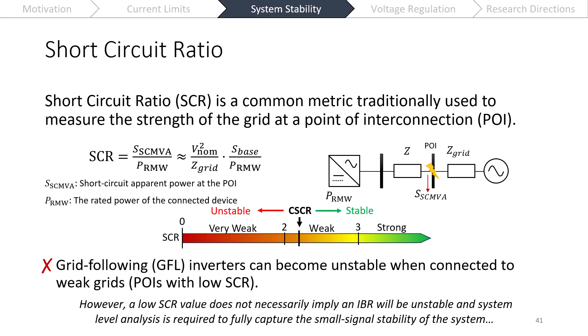And to actually be able to understand stability, we have to do more of a system-level analysis, considering how devices might interact, and then also derive something called the critical short circuit ratio, which is essentially just the SCR value for our system, that if it's below that value, will be unstable. If it's above that value, our device will be stable. So you can see here, SCR isn't able to fully consider stability very well without having to actually simulate the system, finding what this critical SCR value is.